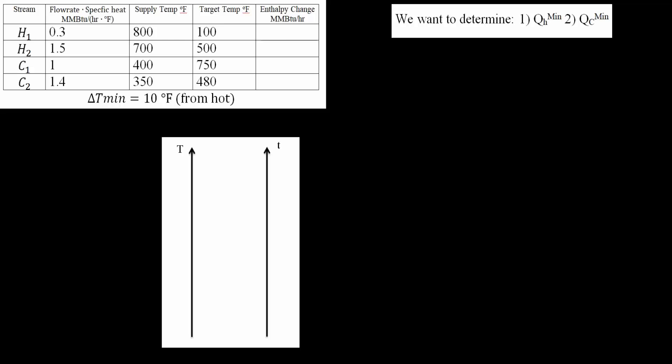To calculate the enthalpy change, it's your flow rate times specific heat times target temp minus supply temp. So for H1: 0.3 times (100 minus 800) gives negative 210. For H2: 1.5 times (500 minus 700) gives negative 300. For C1: 1 times (750 minus 400) gives positive 350. And for C2: 1.4 times (480 minus 350) gives positive 182.